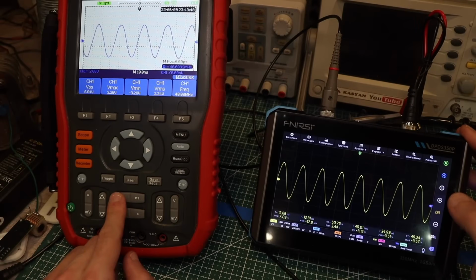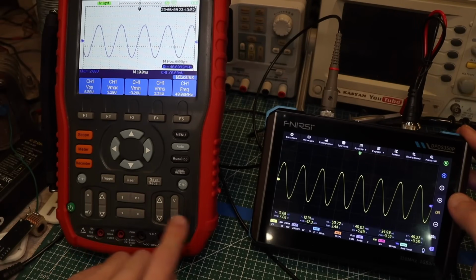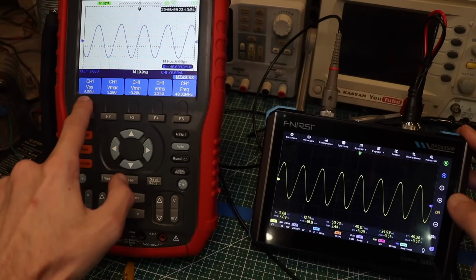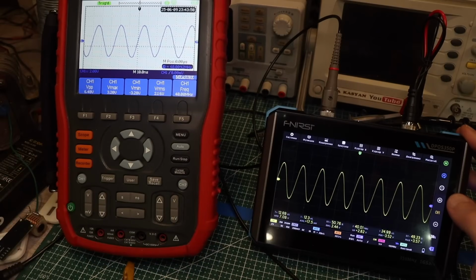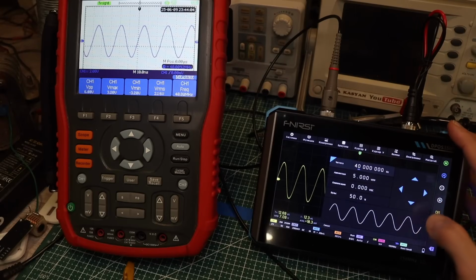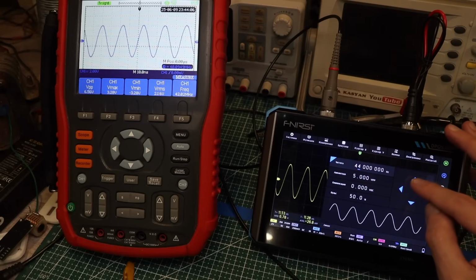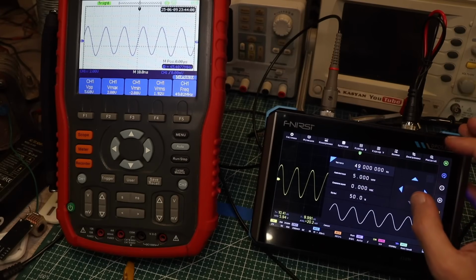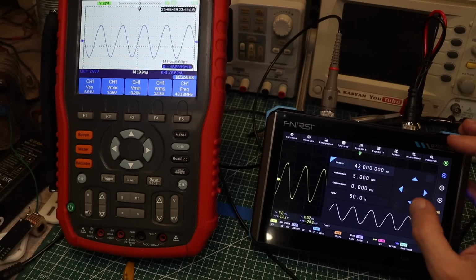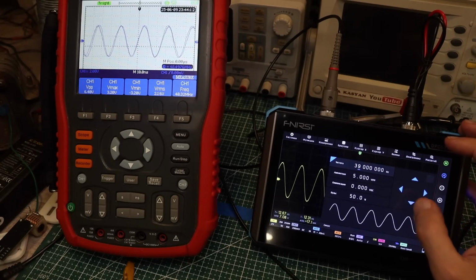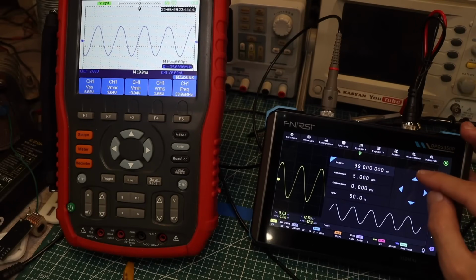Both devices started showing slightly higher peak-to-peak values, about 7 volts here, and the same, around 6.6, maybe 6.7 volts on this device. This means that our generator slightly overstates the amplitude at these frequencies, which is expected because we're already close to its limit. And now it's starting to understate it. You can clearly see that. Right now, up to about 40 megahertz.